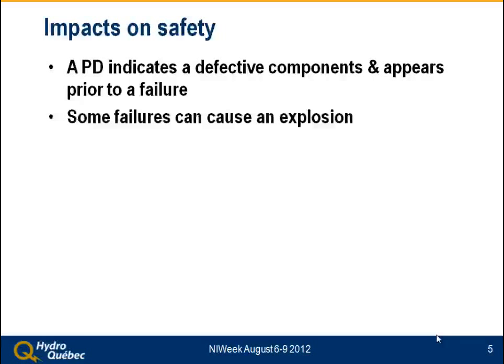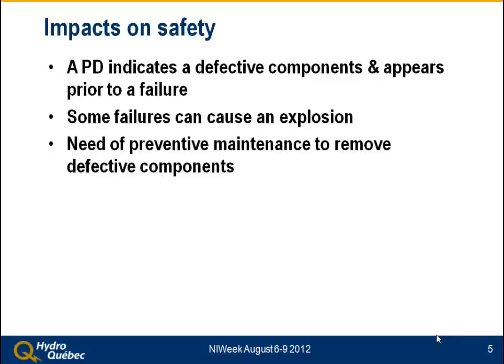Why can it explode? Because all those accessories are made of plastic, polymers and so on, and when there's a breakdown inside, it burns and releases gases inside the vault. As it is closed, if there is an ignition, it can cause an explosion. If there is a worker inside at the same time, it's not good for him or for the company. So what we want is to do preventive maintenance and remove those defective components before any accident.